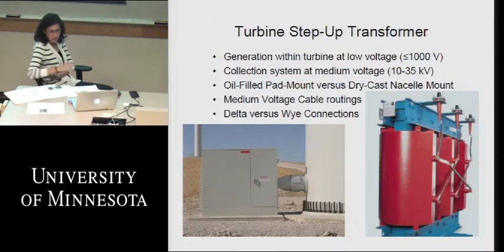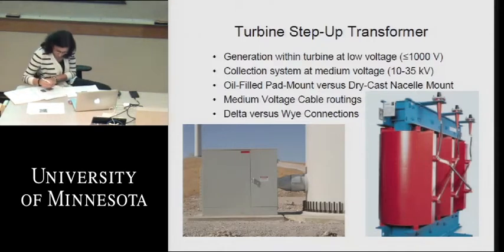The last major item about transformers to consider is, well, there's kind of two things. One thing is that you don't necessarily have to have an extra 25% oversize of the transformer with the wind turbine. You can size it to 100% of the apparent power output of the wind turbine itself. The reason is that as wind picks up and generates more power, it creates more current, which would heat up this transformer, and it also tends to help cool the transformer because its rating is based on the cooling designs, whether it's natural cooling, or forced air cooling, or oil cooling.